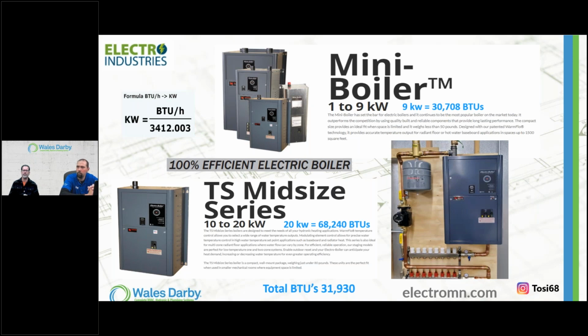But then you go into what you're going to build, right? So the one was packaged, and this is what you're going to build. This would be more traditional. You can actually piggyback this to any existing maybe boiler. You bring the return of the system, flow through, and then out and back to the return of the boiler. Maybe they added an addition. Maybe they want a redundancy. I want to choose when to use one over the other. The cost factor. Wow, the fuel cost went up. My electric is low. I'll use this. And then I have the ability to switch. I can just flip a switch on the electric, use electric or bypass.